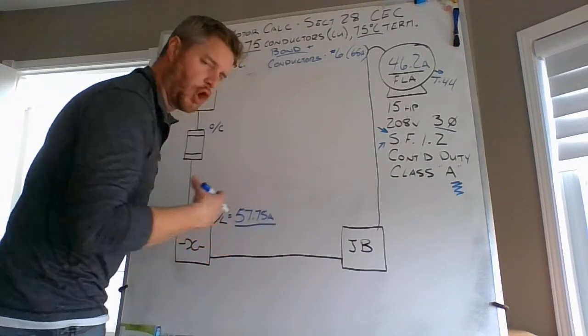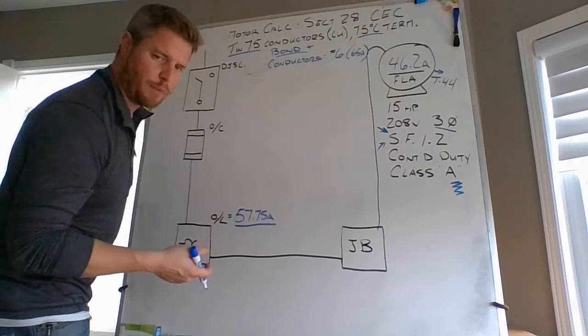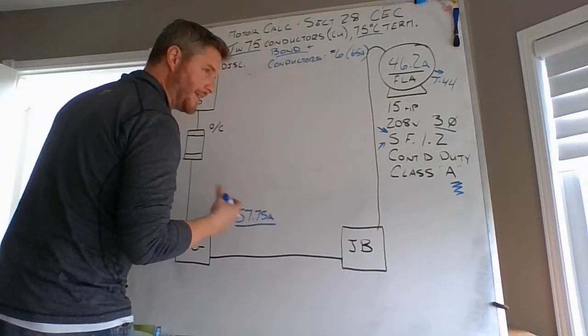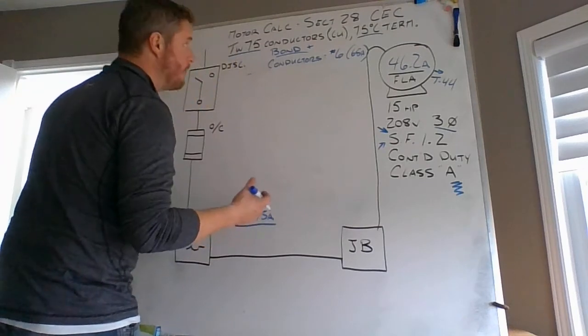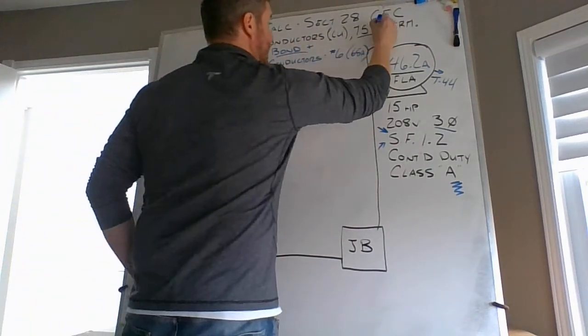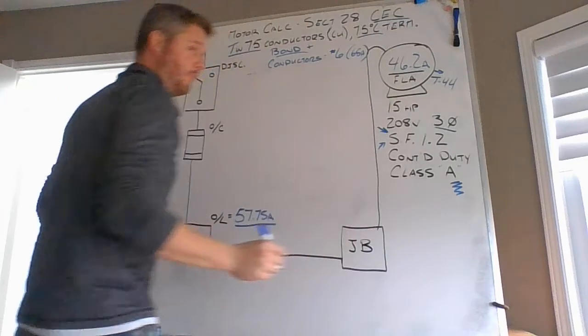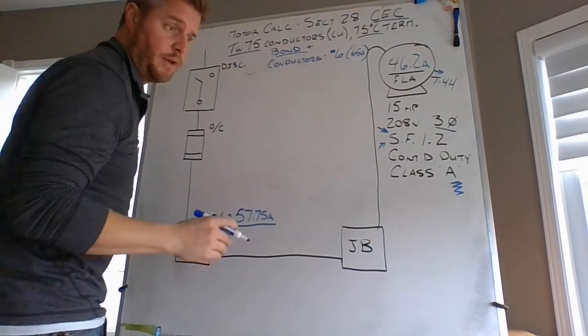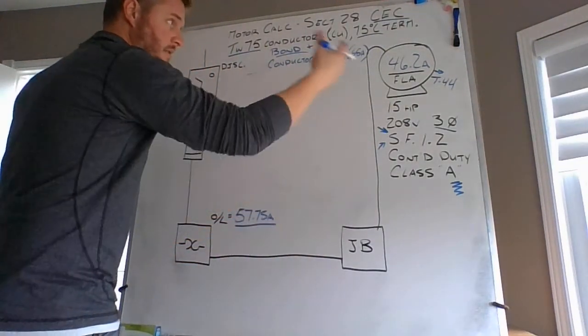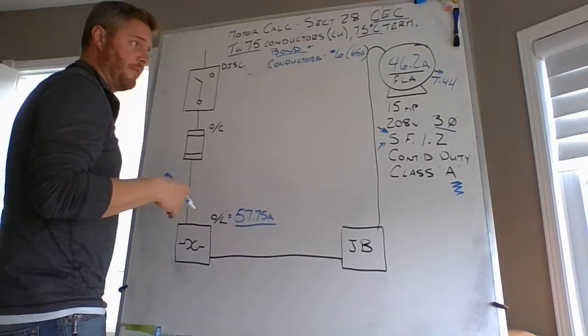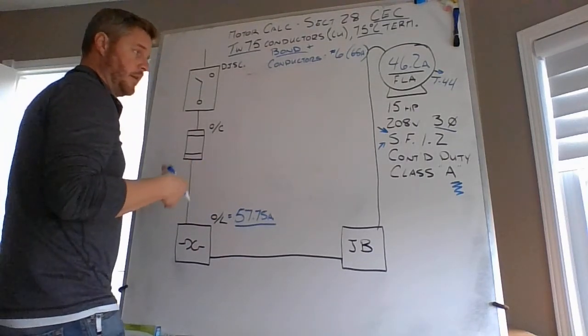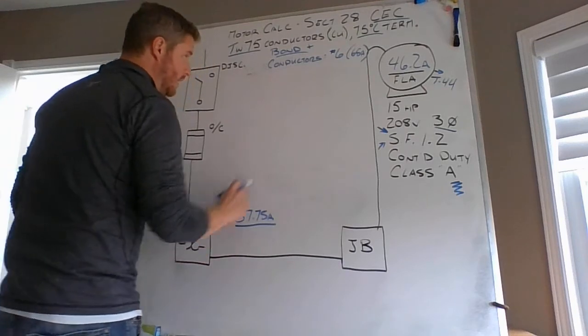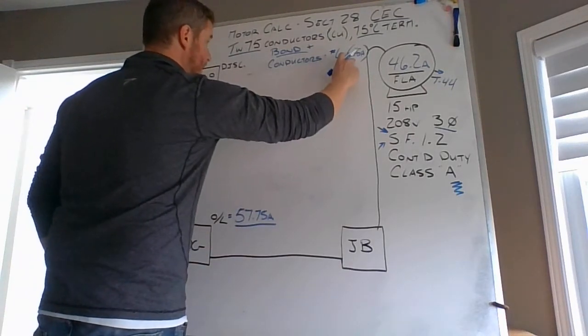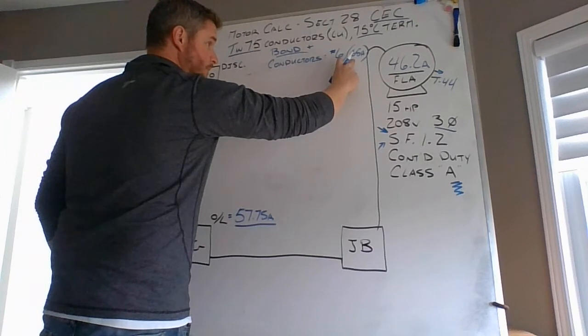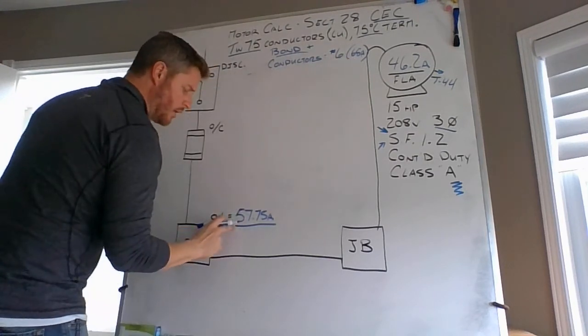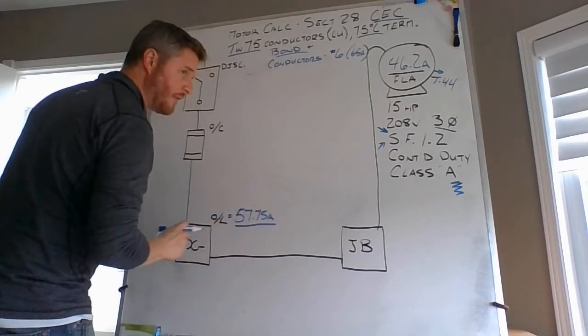And they'll allow a little more current for inrush to get that motor up to speed, but only for a short period of time. And keep in mind, you're going from the Canadian Electrical Code Book here. I'm showing you the code rules to suffice this 15 horsepower, 208 volt, 3-phase motor. So your overloads are protecting your conductors. Your conductors are rated or set for 65 amps. And your overloads are set to trip at 57.75 amps.